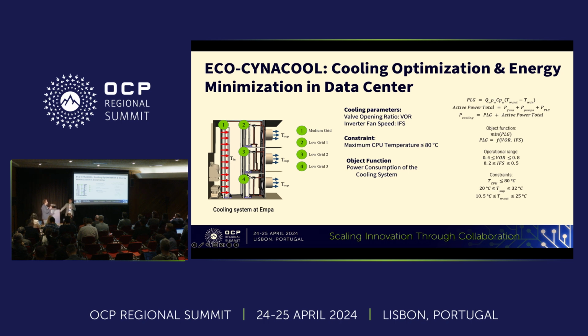Our first constraint was CPU temperature, so we tried to keep this value close to the threshold. When we observed the inlet temperatures, we noticed they had increased beyond the standard or suggested values by ASHRAE, for example. This increase provided a gain in energy saving in the ECO-Qube project.